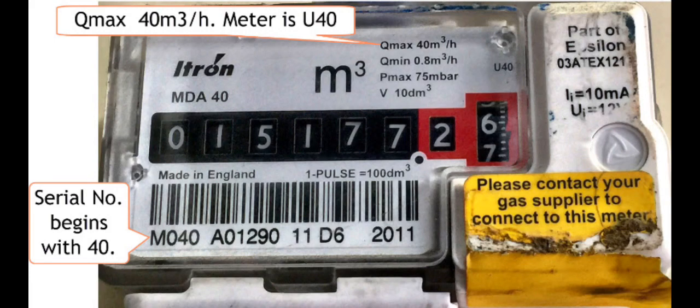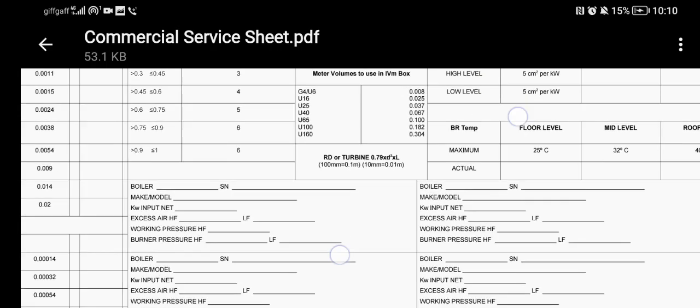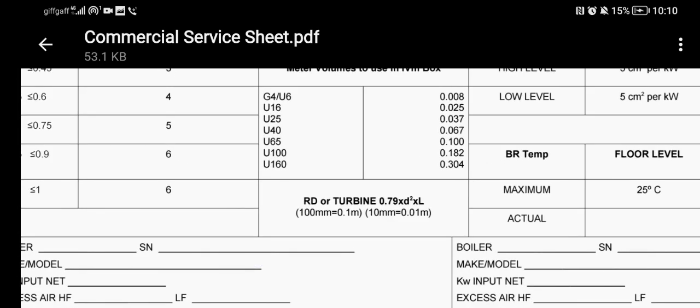You can see here this is a U40, and also look at the Q max — the quantity max that it lets through per hour. In this picture, can you see the Q max? Q max helps me identify what meter it is. It's a U40 meter letting through 40 cubic metres per hour of gas. Do you see the serial number at the bottom — it says M040 — that's also helping me identify the meter. Then you look in your book under meter volumes and look at what type of meter it is, like the U40, to find out the volume.